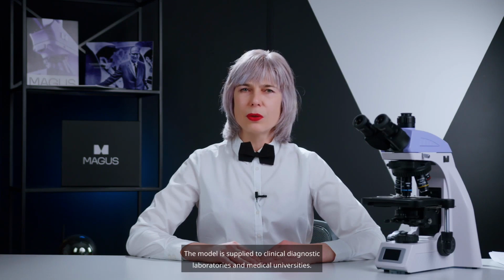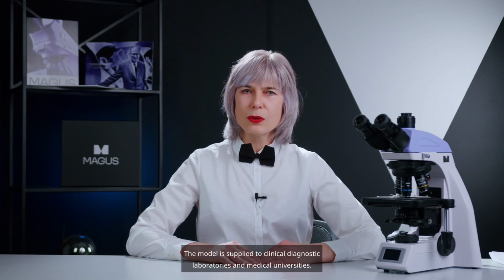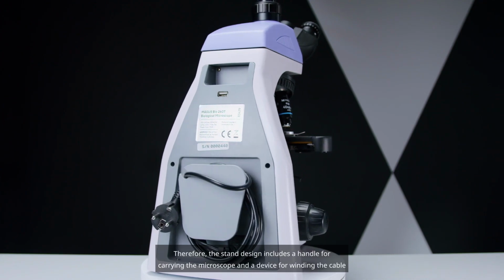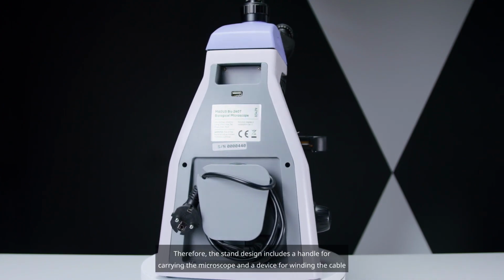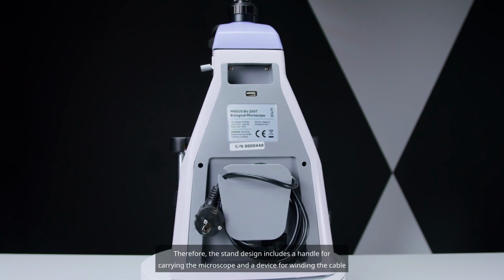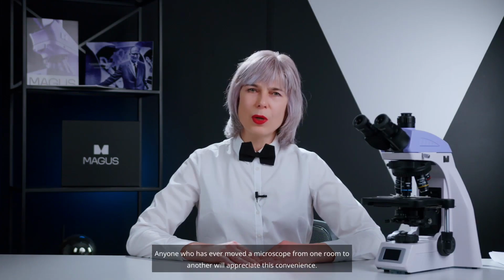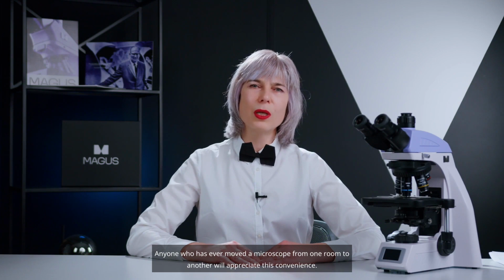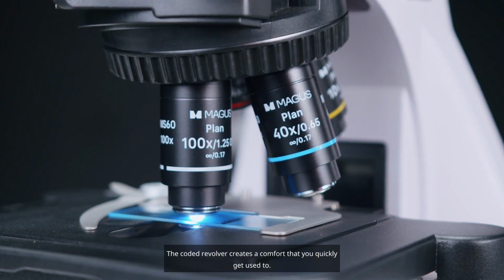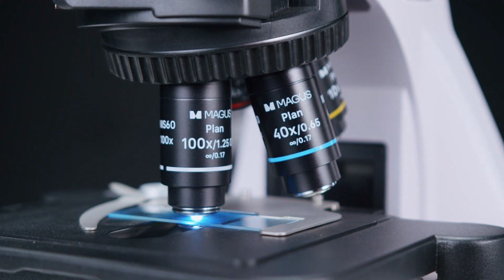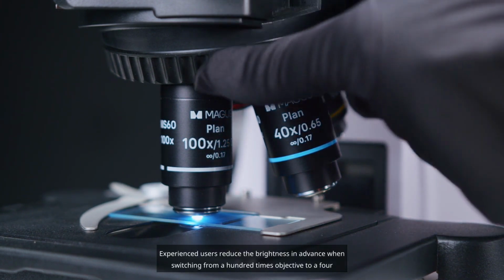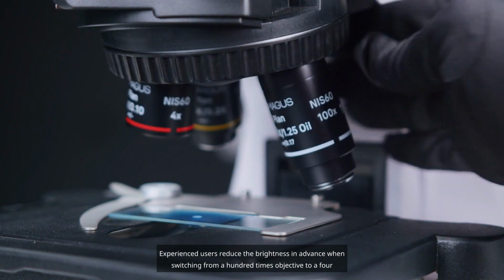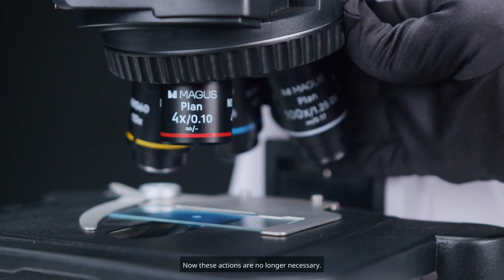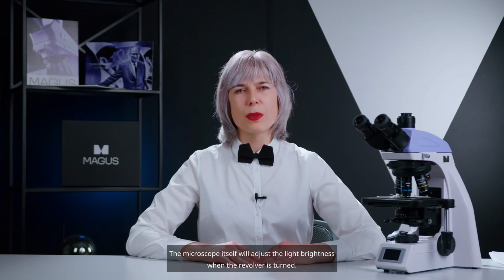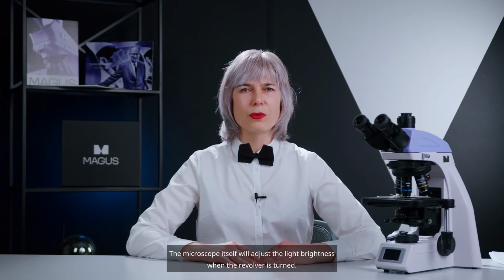The model is supplied to clinical diagnostic laboratories and medical universities. Therefore, the stand design includes a handle for carrying the microscope and a device for winding the cable. Anyone who has ever moved a microscope from one room to another will appreciate this convenience. The coded revolver creates a comfort that you quickly get used to. Experienced users reduce the brightness in advance when switching from a 100 times objective to a 4 times objective. Now these actions are no longer necessary. The microscope itself will adjust the light brightness when the revolver is turned.